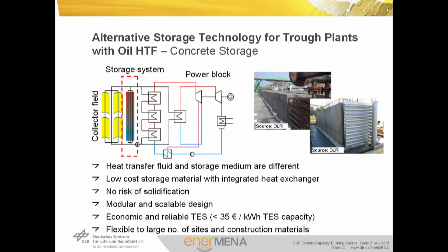An alternative approach to reduce storage material costs is to use solid storage media instead of molten salt. An attractive candidate is concrete as storage material. For these systems, the heat transfer fluid is different from the storage medium. Low-cost storage materials are used in combination with an integrated heat exchanger. There is no risk of solidification. The design is modular and easily scalable. Analysis shows an economic and reliable thermal energy storage system could be implemented at less than 35 EUR per kWh, with an option to use locally available construction materials.